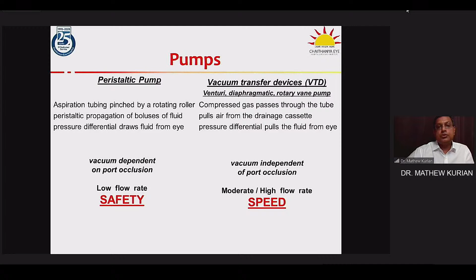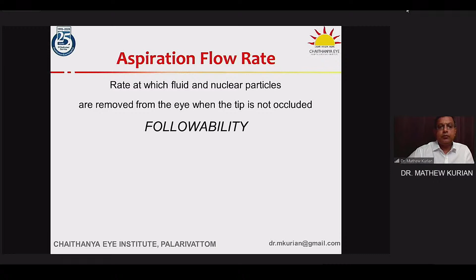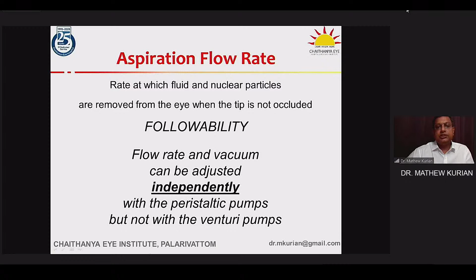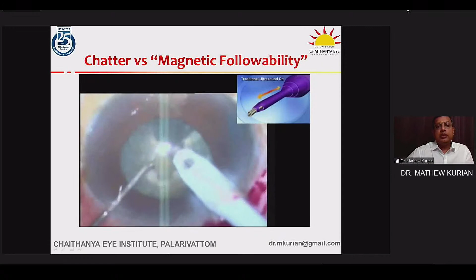in the eye. The aspiration flow rate is the rate at which the fluid and nucleus particles are removed from the eye when the tip is not occluded, and this is applicable only to the peristaltic machines. You can call it followability, the speed with which a nucleus fragment comes to the tip. The flow rate can be independently adjusted from the vacuum in the peristaltic machines, but not with the Venturi machines. With a good flow, there will be no chatter. The piece will not be flying around like this, repulsed by the tip.